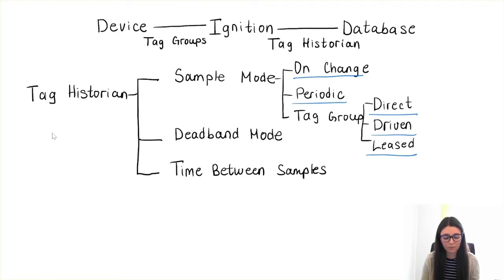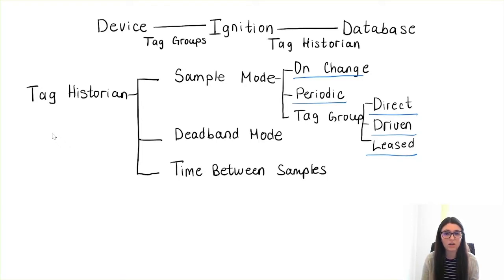The periodic mode is a tricky one, because if we are dealing with a lot of tags, we may end up with large amounts of data. The periodic mode works on a specific execution rate — for example, if we set it to one second, then every second a value will be inserted into the database for each tag.